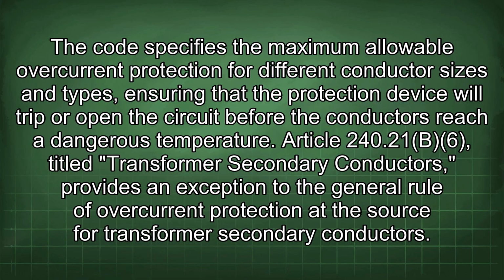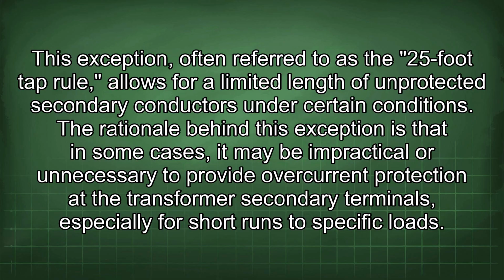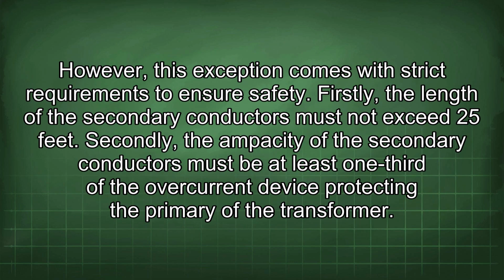Article 240.21(B)(6), titled Transformer Secondary Conductors, provides an exception to the general rule of overcurrent protection at the source for transformer secondary conductors. This exception, often referred to as the 25-foot tap rule, allows for a limited length of unprotected secondary conductors under certain conditions. The rationale behind this exception is that in some cases, it may be impractical or unnecessary to provide overcurrent protection at the transformer secondary terminals, especially for short runs to specific loads. However, this exception comes with strict requirements to ensure safety.